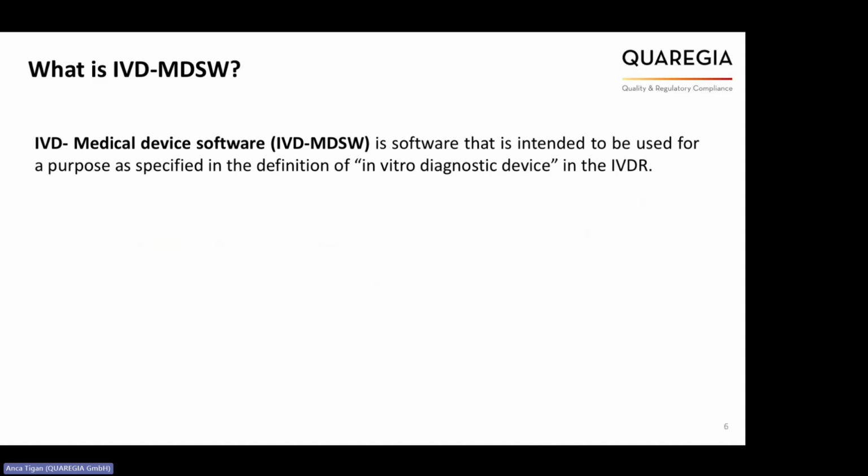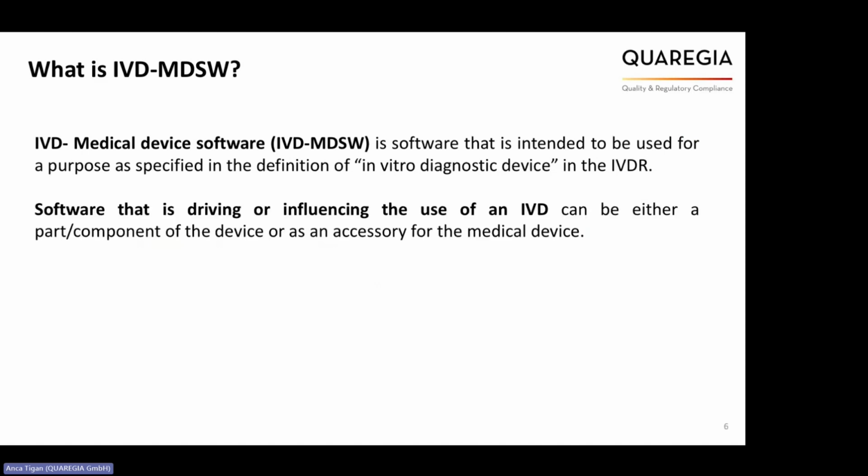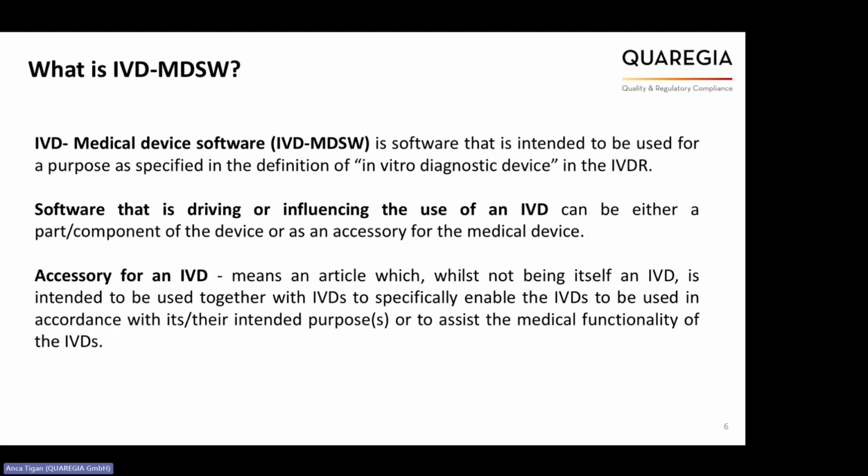What is important to know at this point is that software that is driving or influencing the use of an in vitro diagnostic device can be either a part or component of the device or can be classified or qualified as an accessory for the medical device. And for this, we just quickly look at what an accessory is, and then we go into more practical examples.